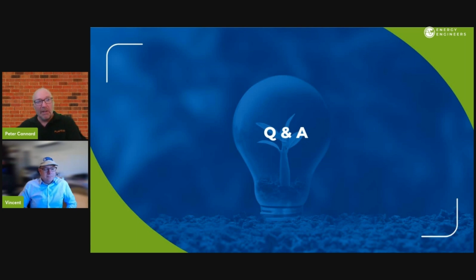So it's quite an expensive afterthought. These are large applications - large pumping systems, large motor controllers that are 2 meters high, about 0.5 to 3/4 meter wide, in little switch rooms out in remote areas. Now they've got to somehow cut that switch room in half and extend it to fit an extra harmonic filter. It's a very expensive afterthought, so engineering is definitely good to do before those types of installations.